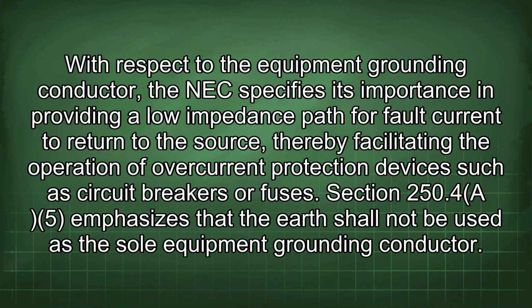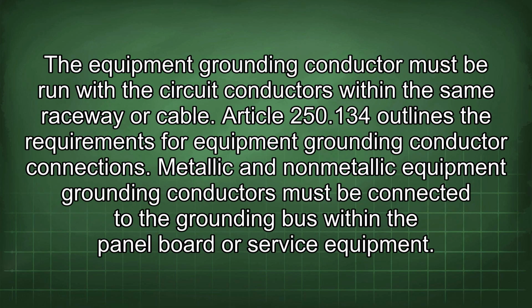With respect to the equipment grounding conductor, the NEC specifies its importance in providing a low impedance path for fault current to return to the source, thereby facilitating the operation of overcurrent protection devices such as circuit breakers or fuses. Section 250.4(A)(5) emphasizes that the earth shall not be used as the sole equipment grounding conductor. The equipment grounding conductor must be run with the circuit conductors within the same raceway or cable.